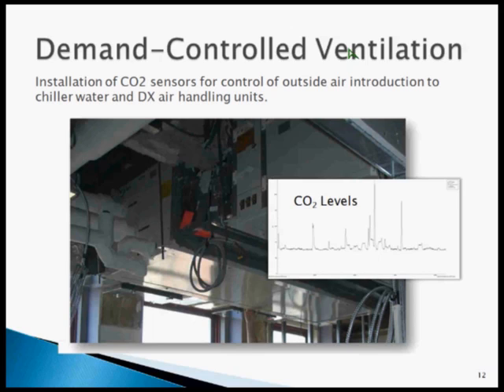Everybody knows about ASHRAE 62, right? In this building right here, how many CFM of outside air? How do you say fresh air? Outside air. You don't know exactly if it's fresh or not. How many cubic feet per minute of outside air do we need for each of us in this room right now? You're close. You're closer. 15 is schools, but for an office building, 20.